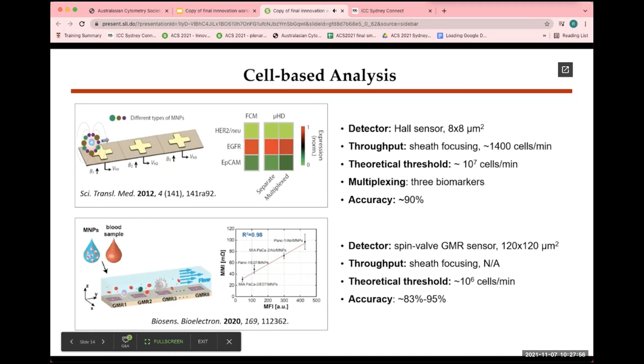In addition to cell-based analysis, we further extended the application of magnetic cytometry to multiplexed biomolecular analysis. This is also one of the major applications of conventional optical flow cytometers. The relevant technology is so-called suspension array technology, and that has typically been based on fluorescently barcoded microparticles as the molecular carriers. So for magnetic flow cytometry, we are developing magnetically encoded microparticles, and the particles can be differentiated by their unique magnetic stray field patterns. Eventually, we could use GMR sensors, like those used already in computer hard disk drives, to read out these patterns.